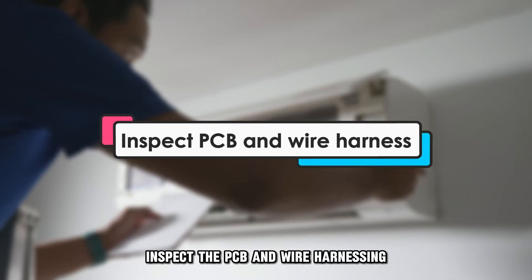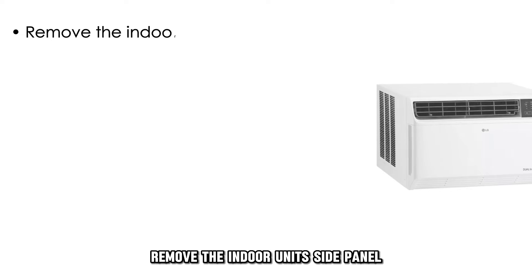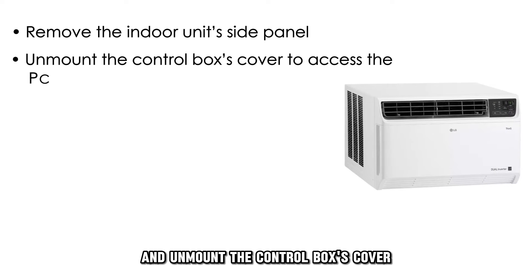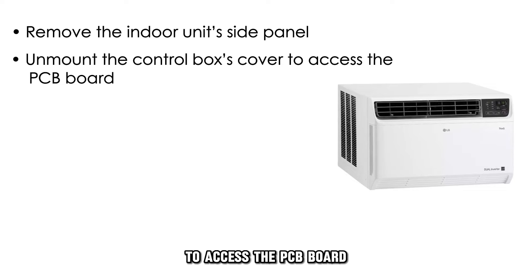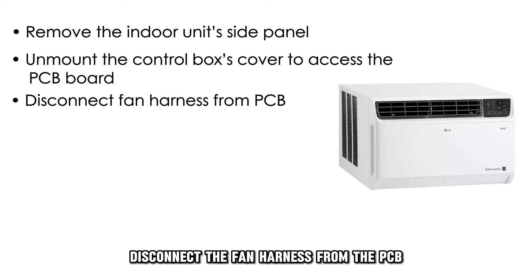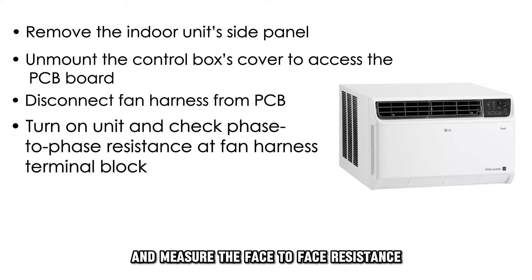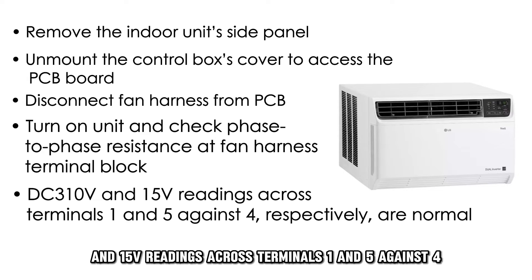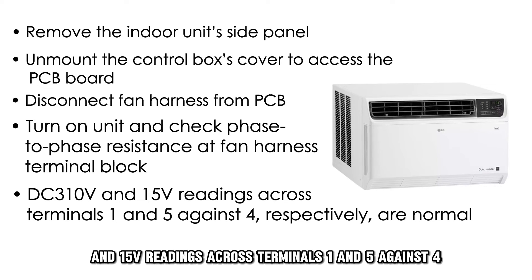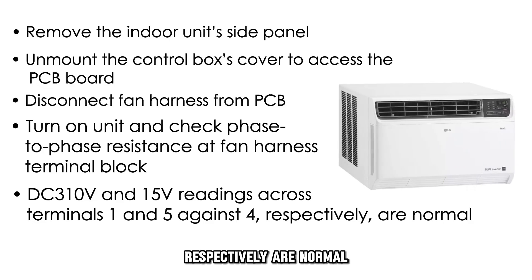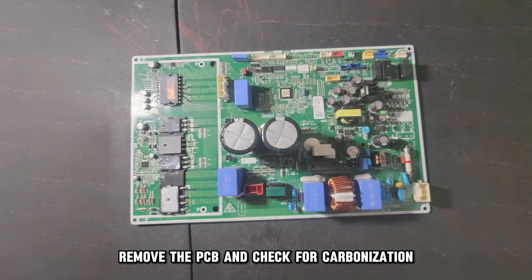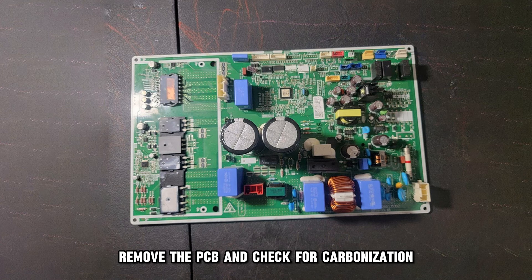Inspect the PCB and wire harnessing. Remove the indoor unit's side panel and unmount the control box's cover to access the PCB board. Disconnect the fan harness from the PCB, turn the unit on, and measure the phase-to-phase resistance across the terminal block where the fan harnesses connect. DC 310V and 15V readings across terminals 1 and 5 against 4 respectively are normal. Remove the PCB and check for carbonization on its rear side. Inspect the PCB for chars and replace the PCB if necessary.